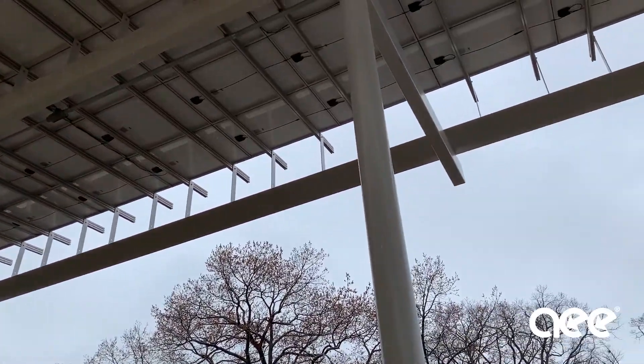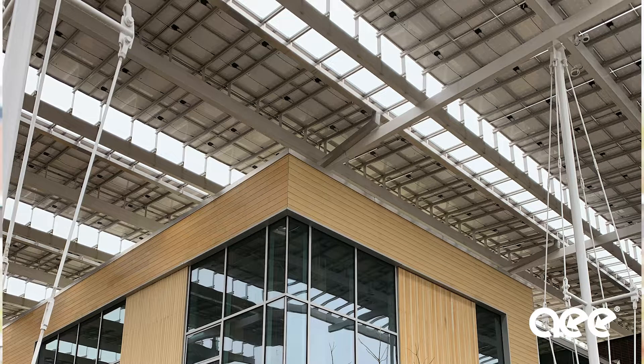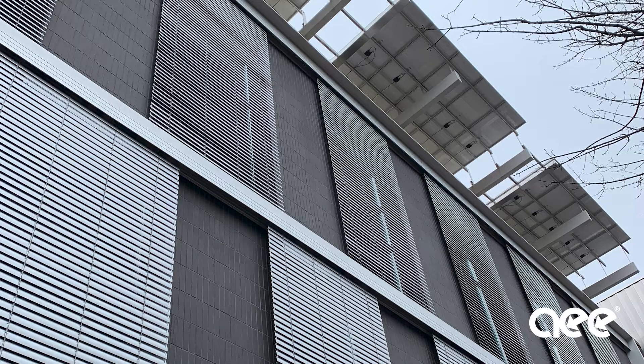We're here underneath the solar canopy of the Georgia Tech Kendeda Building. It is a 330 kilowatt PV array consisting of some of the most efficient solar modules available, called SunPower — 22% efficiency modules that comprise all of the building's energy production, creating a net positive result of 40%. Over a thousand of these highly efficient modules are installed. They have one of the best temperature coefficients on the market, and their degradation per year is considerably less than a standard module, ensuring the building remains net positive year after year for a full 20 years.